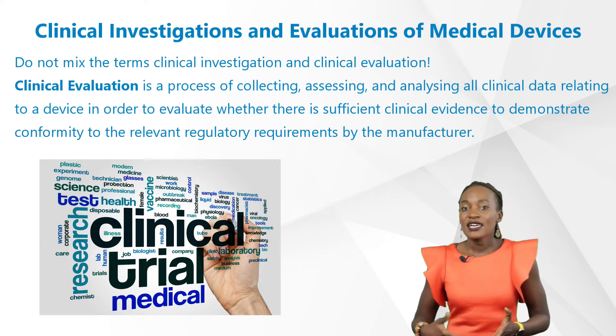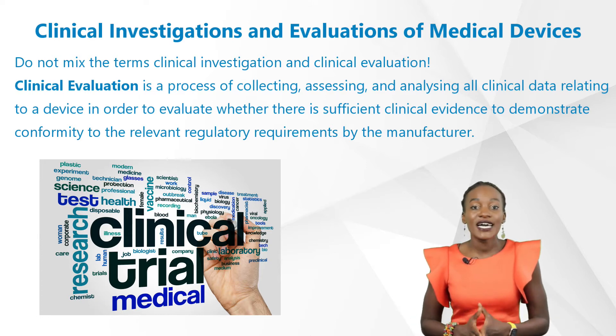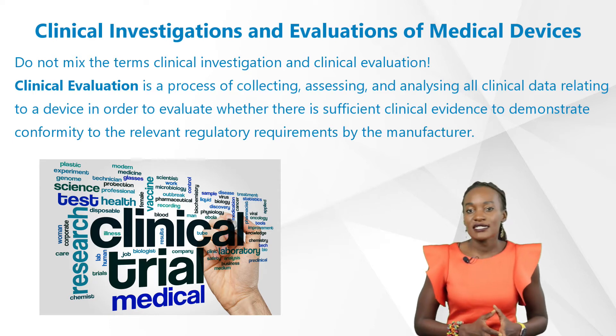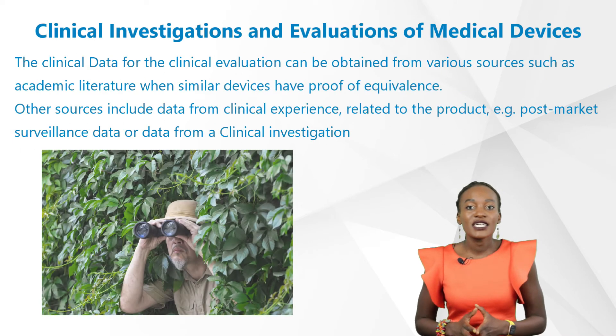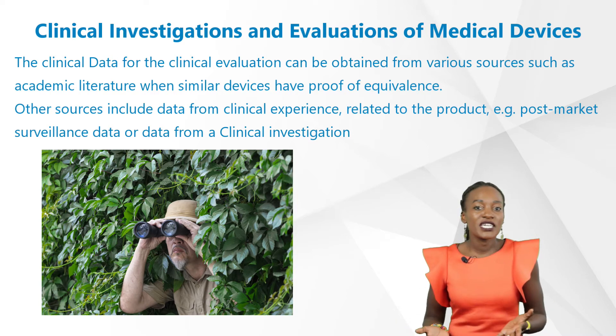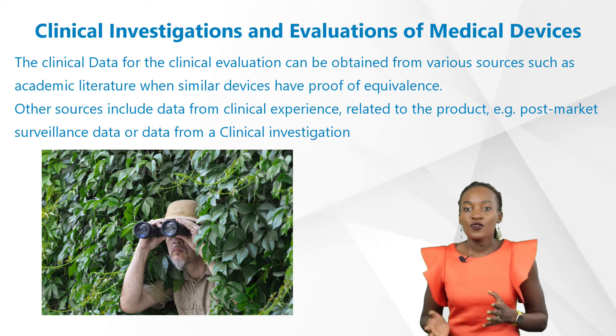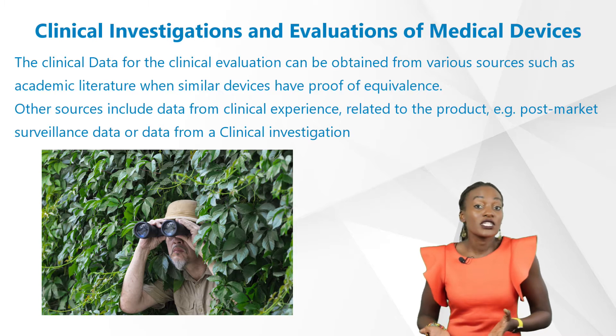It's important not to mix the terms clinical investigation and clinical evaluation. Clinical evaluation is a process of collecting, assessing, and analyzing all clinical data relating to a device in order to evaluate whether there is sufficient clinical evidence to demonstrate conformity to the relevant regulatory requirements by the manufacturer. The clinical data for the clinical evaluation can be obtained from various sources such as academic literature when similar devices have proof of equivalence — a topic we've also covered in a separate video.